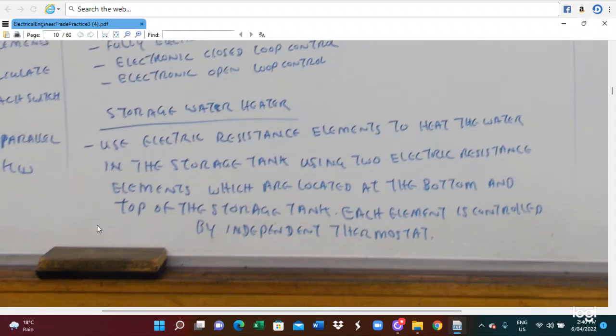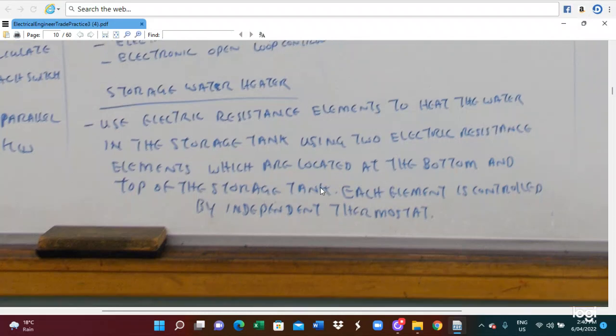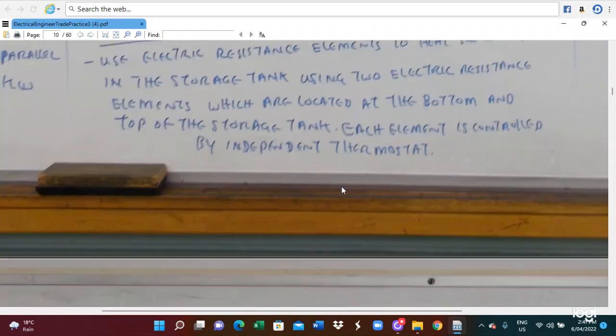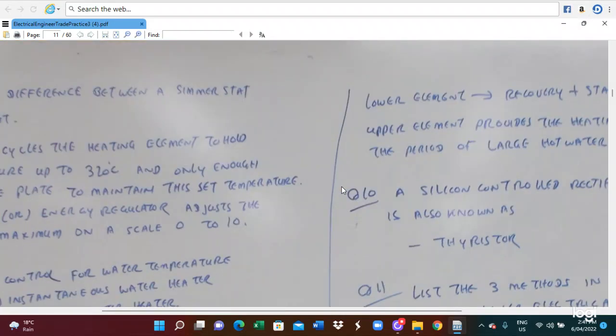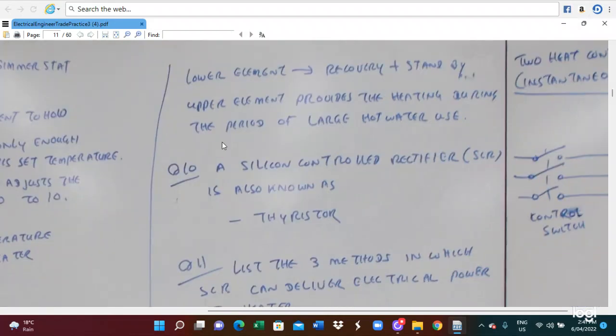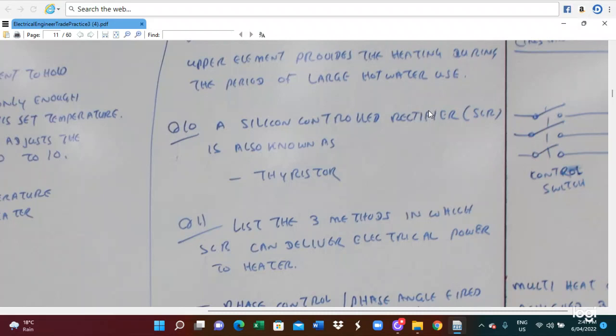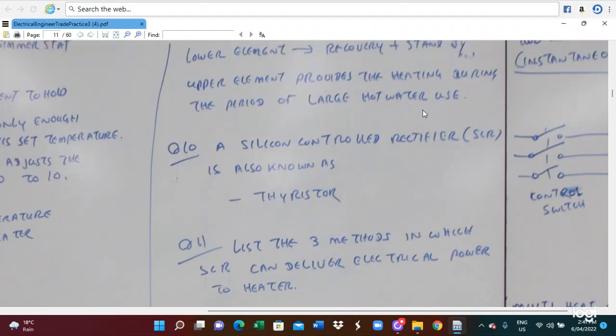In the storage water heater, we use electric resistance elements to heat the water in the storage tank, using two elements located at the bottom and the top of the tank. Each element is controlled by an independent thermostat. The lower element is utilized for recovery and standby. The upper element provides heating during the period of large hot water use.